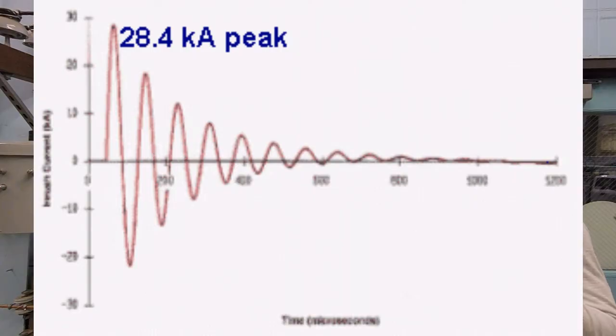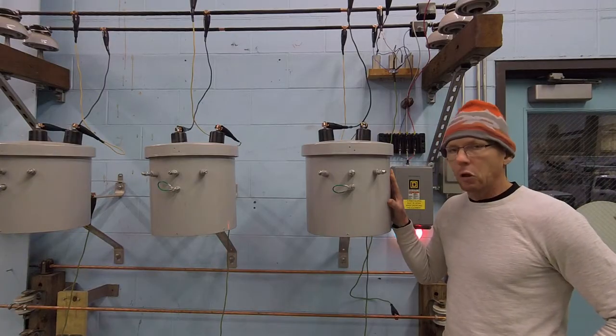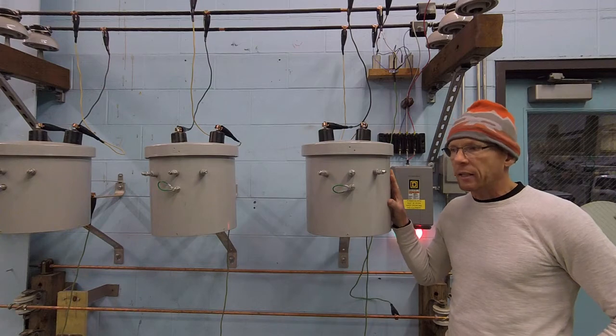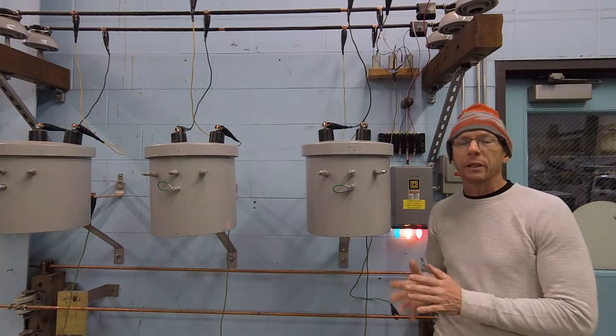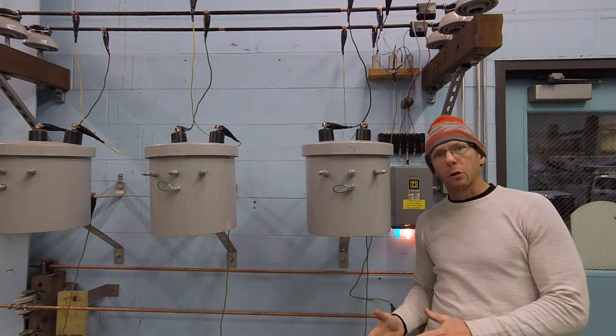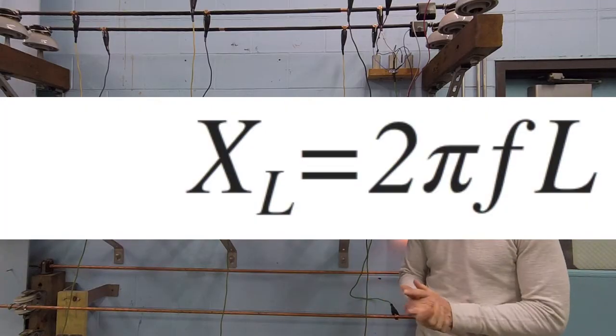During saturation, and we're only talking about a very small period of time, maybe on the order of a few milliseconds, the inductive component of the transformer is fairly low. And what that means is that the impedance it offers reactively to the circuit is also low because inductance and impedance are directly proportional.